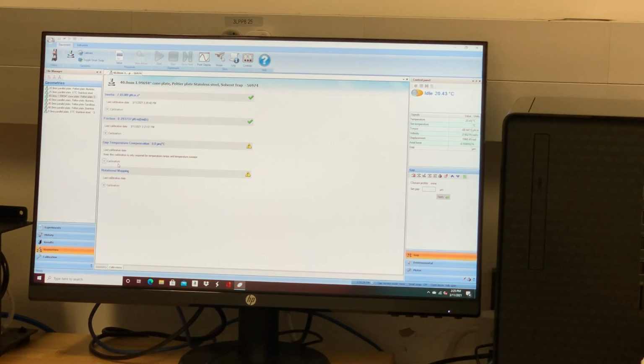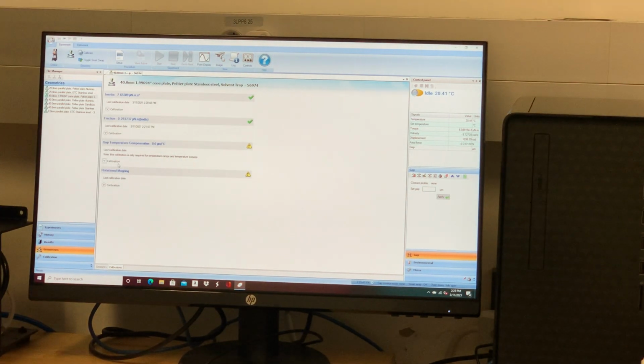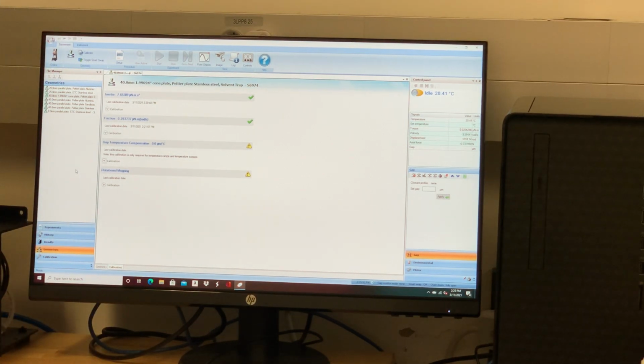Now, we don't do it with a cone. One thing about cones is that the sample gap for a cone is very small, typically 50 microns. So you normally don't run temperature ramps with a cone. You would use a plate. It's hard to control the gap with such a small gap and the heat expansion with a cone. So typically you'll do temperature ramps with a plate, and you don't need to worry about doing that calibration with the cone.